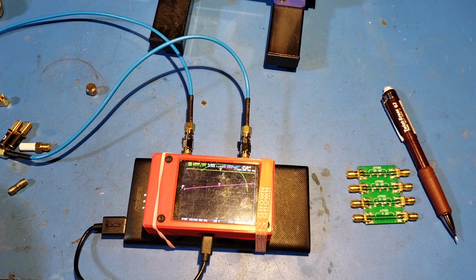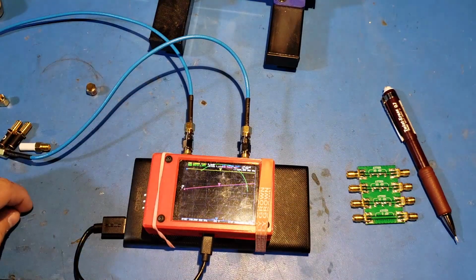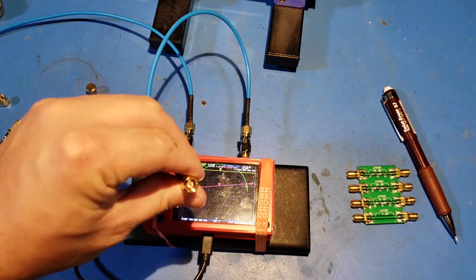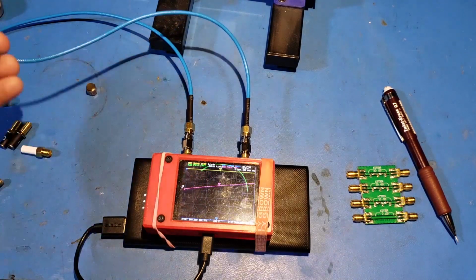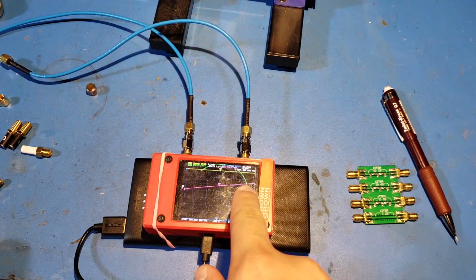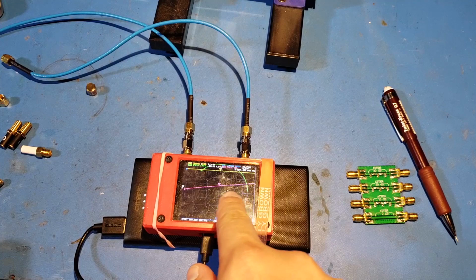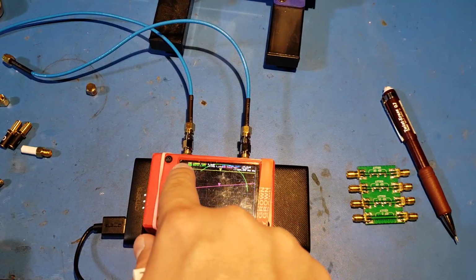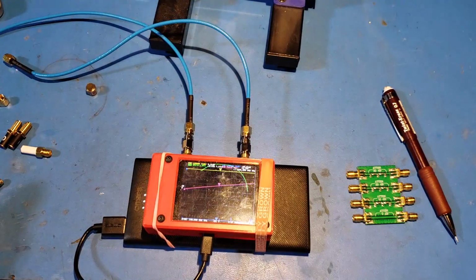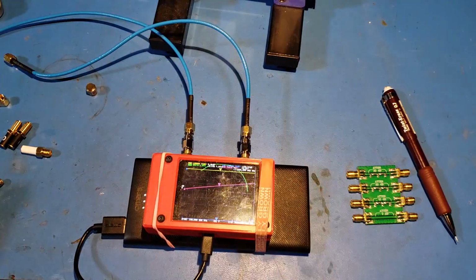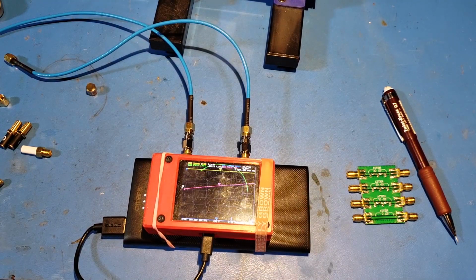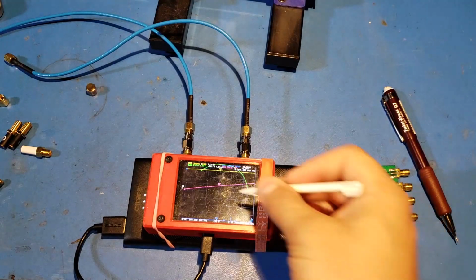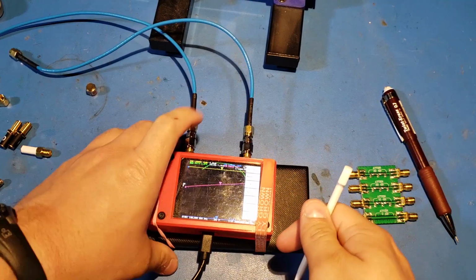For the second calibration, we simply remove the female-to-female SMA connector from the male SMA connector at the end of this piece of coax. Then we'll see that instead of a dot at the open circuit for the valid calibration, we'll see this long line here, where it's on the outside of the Smith chart, but clearly an open circuit is being transformed differently over a wide range of frequencies. To fix this, we go into the settings and we hit display.